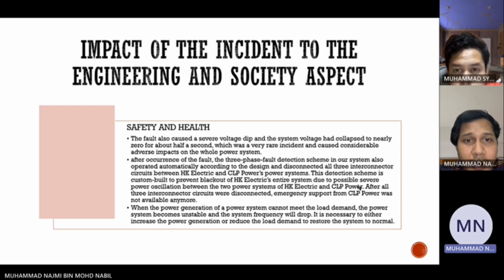After all three interconnector circuits were disconnected, emergency support from CLP Power was not available anymore. And three, when the power generation of a power system cannot meet the load demand, the power system becomes unstable and the system frequency will drop. It is necessary to either increase the power generation or reduce the load demand to restore the system to normal.